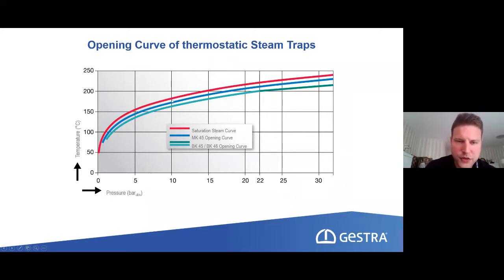And for an MK, this is, let's say, 10 Kelvin below saturation temperature. Compared to that, the BK, the bimetallic one, has to cool down on average roundabout 20 Kelvin. So we have to subcool it by 20 Kelvin, and then the steam trap recognizes, okay, there must be condensate, there cannot be steam, so I have to open. Then the temperature in front of the steam trap will increase again, and 1 or 2 Kelvin before we are back at saturation temperature, the steam trap will close again. With that, we guarantee that we don't have any loss of live steam.